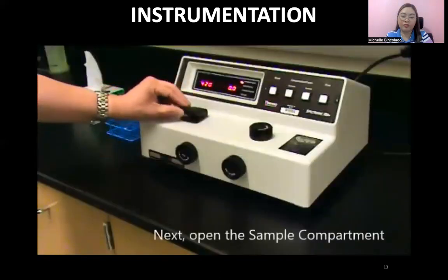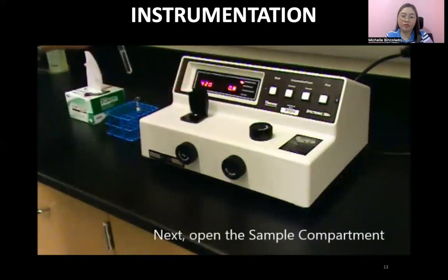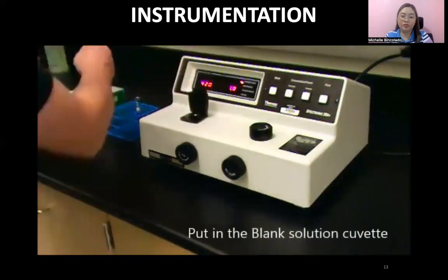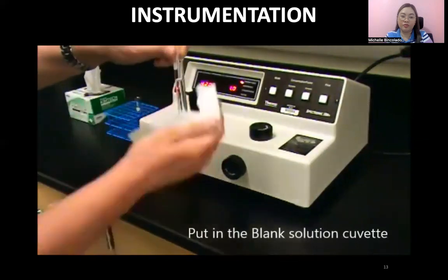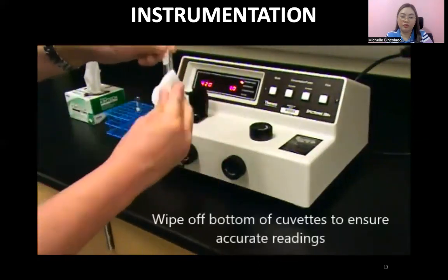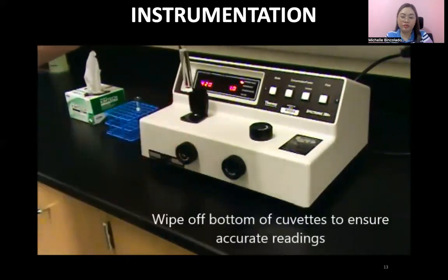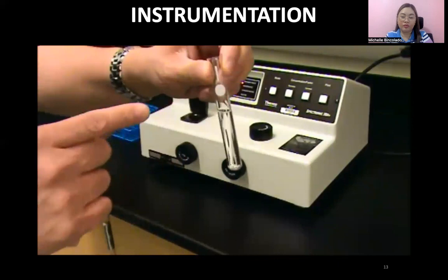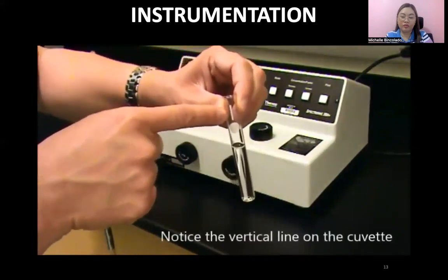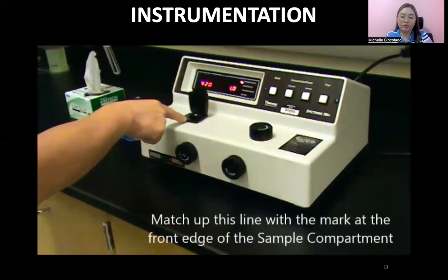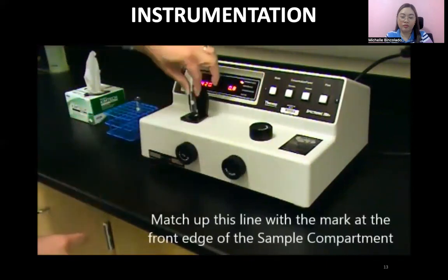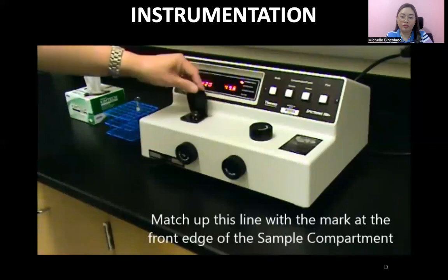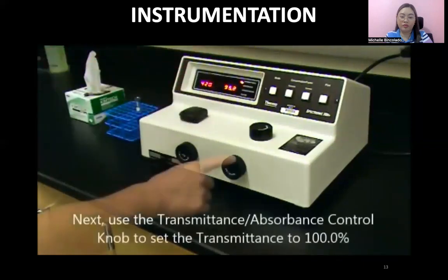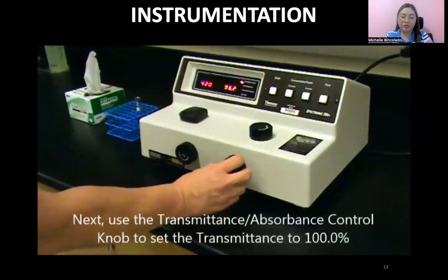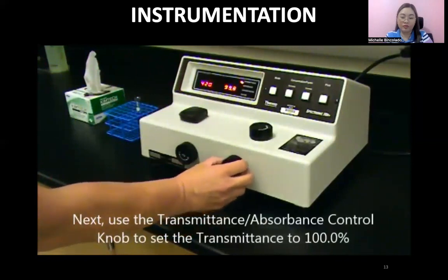Next thing you should do is now open up the sample compartment and put the blank solution in. You should always wipe off the bottom of your cuvettes before you insert them in the machine to make sure that nothing interferes with the reading. Also notice that there's a little line shown in the front of the cuvette. Line that up with the dash on the front of the sample compartment, and then insert it all the way inside, and then close the sample compartment. This time you're going to use the absorbance transmittance control and turn it appropriately one way or the other until you get 100 on the dial.